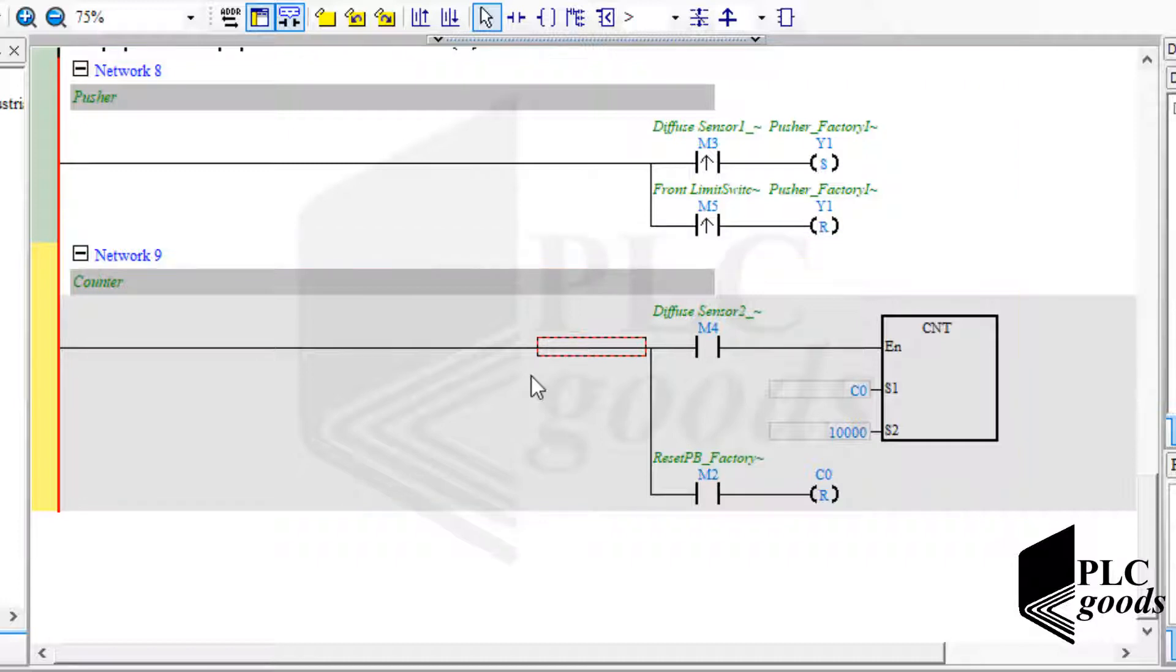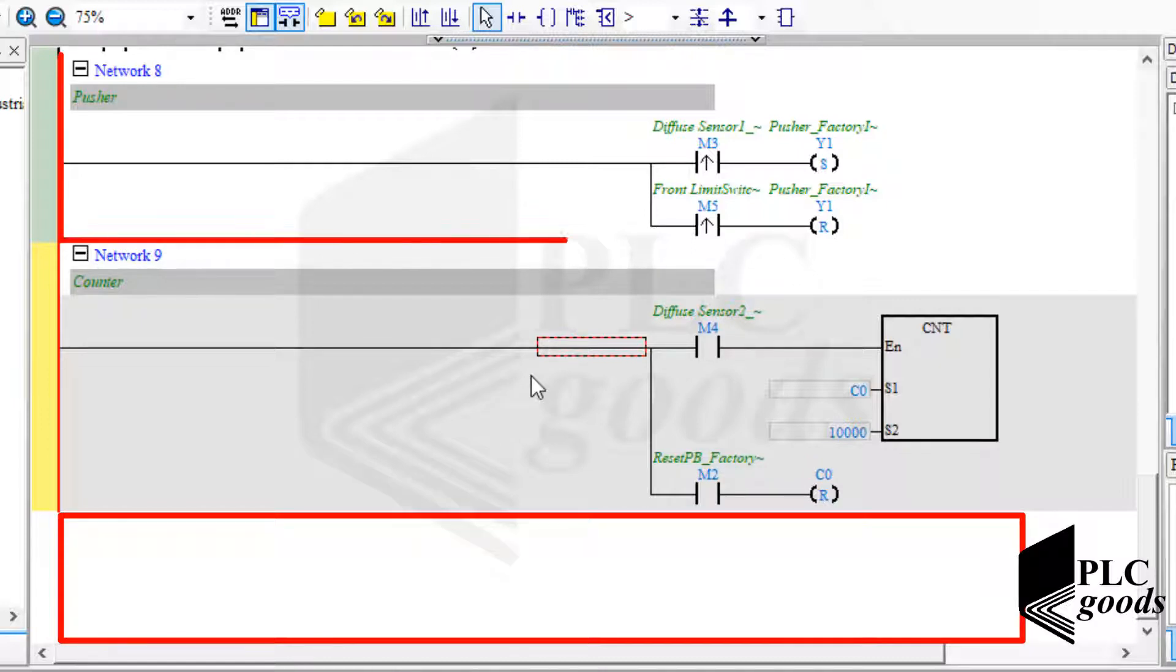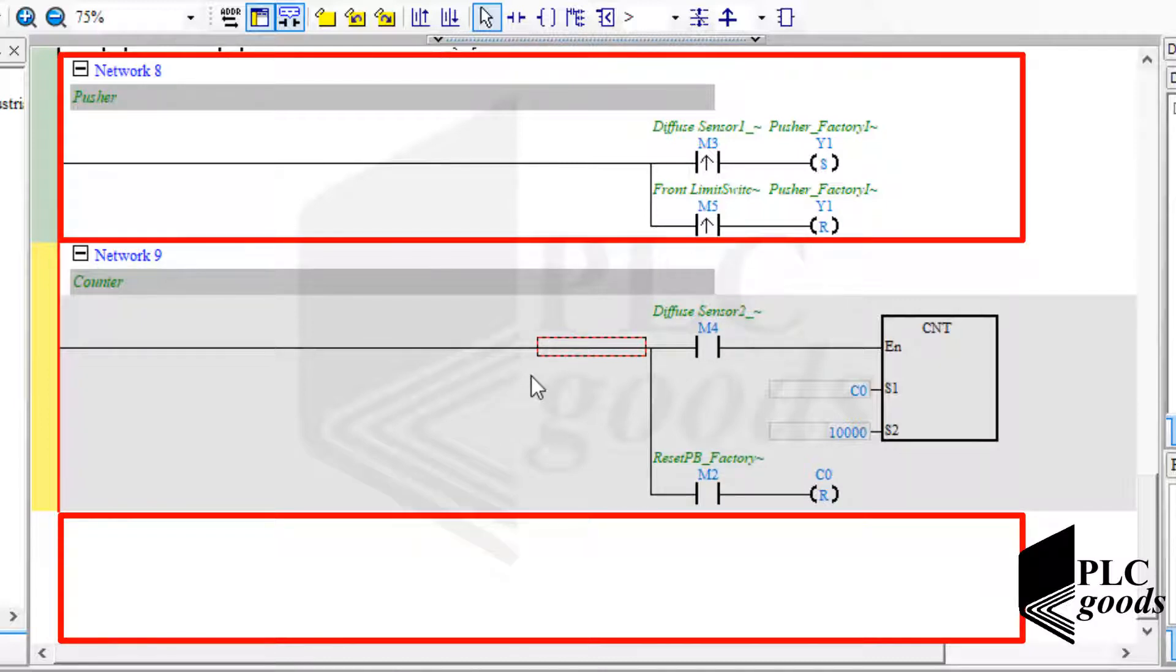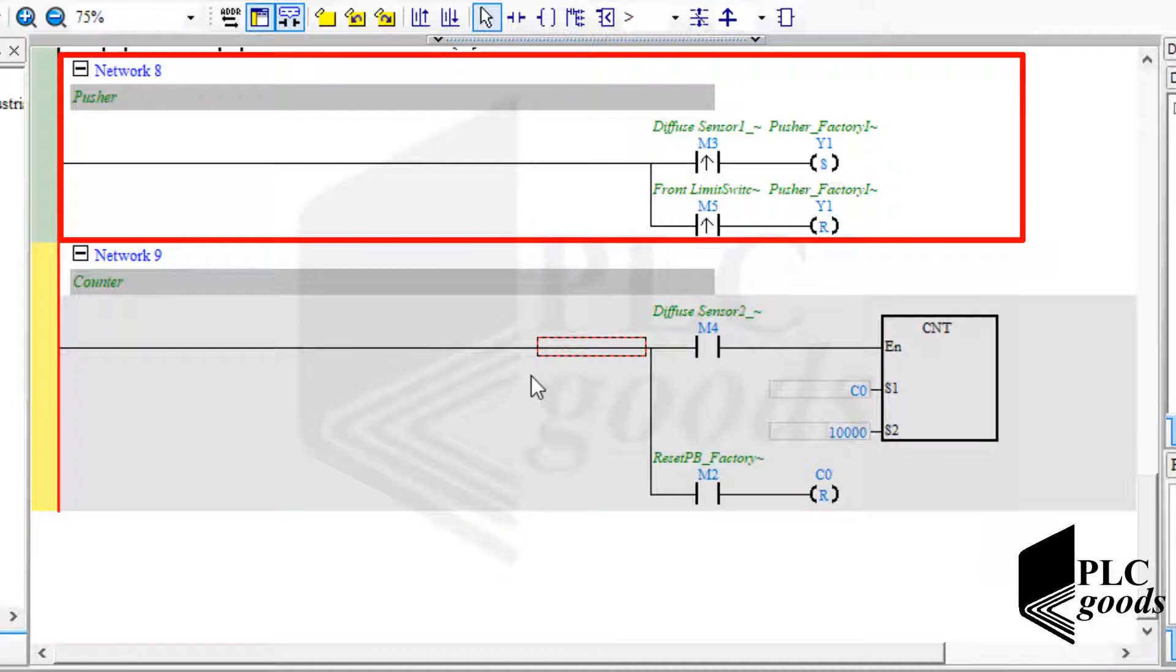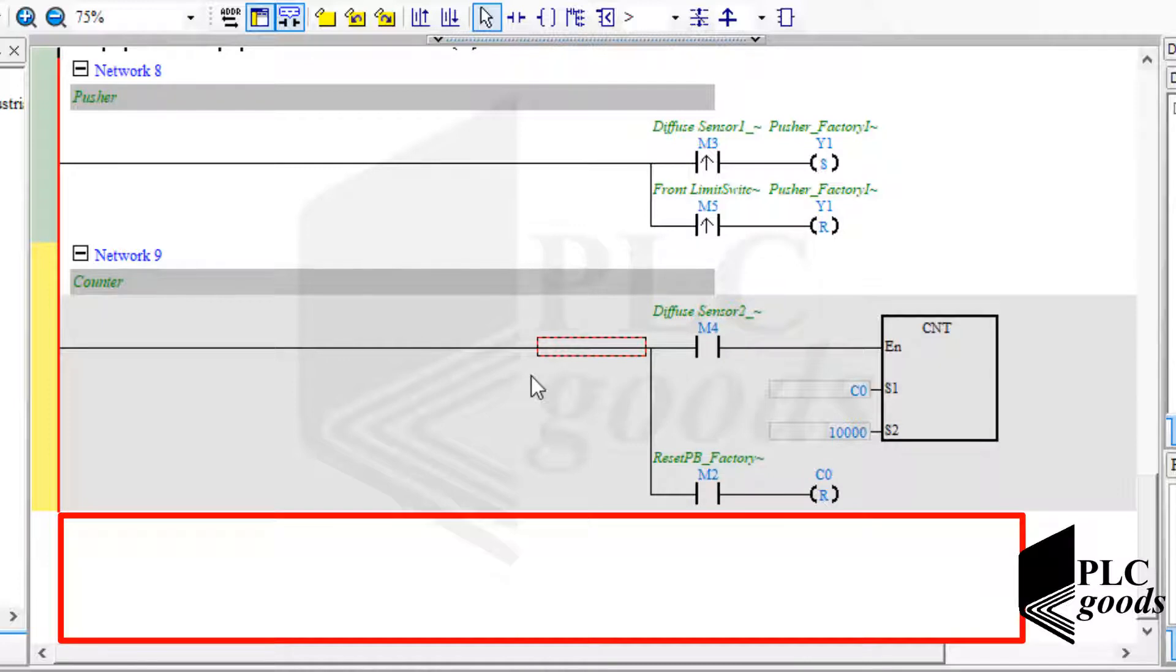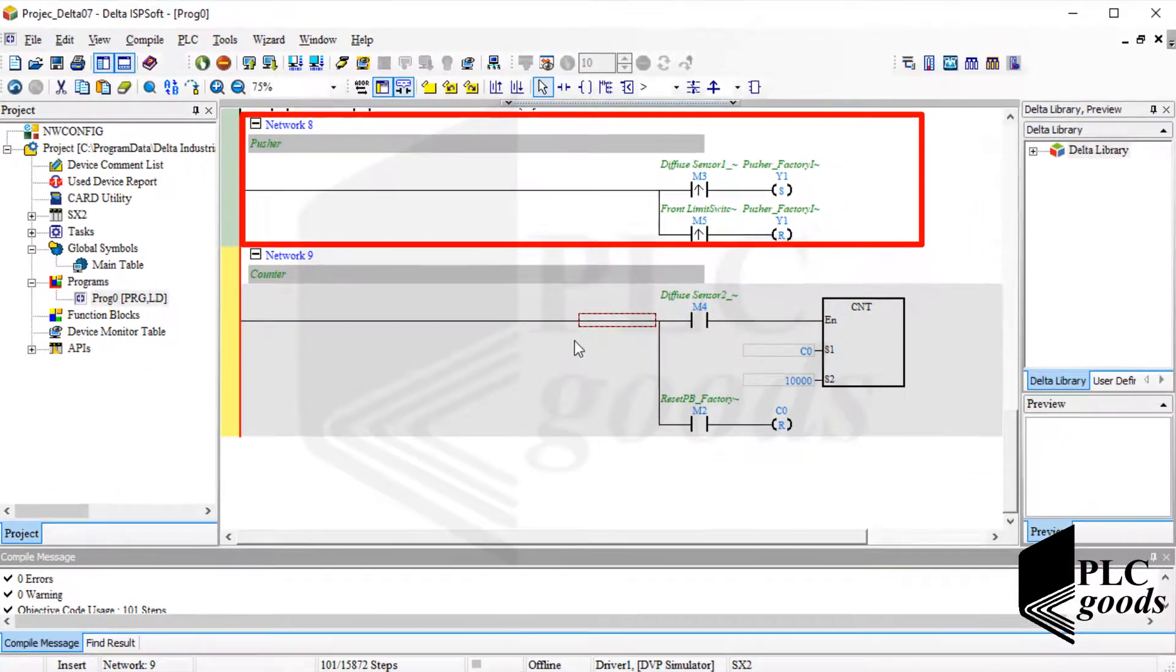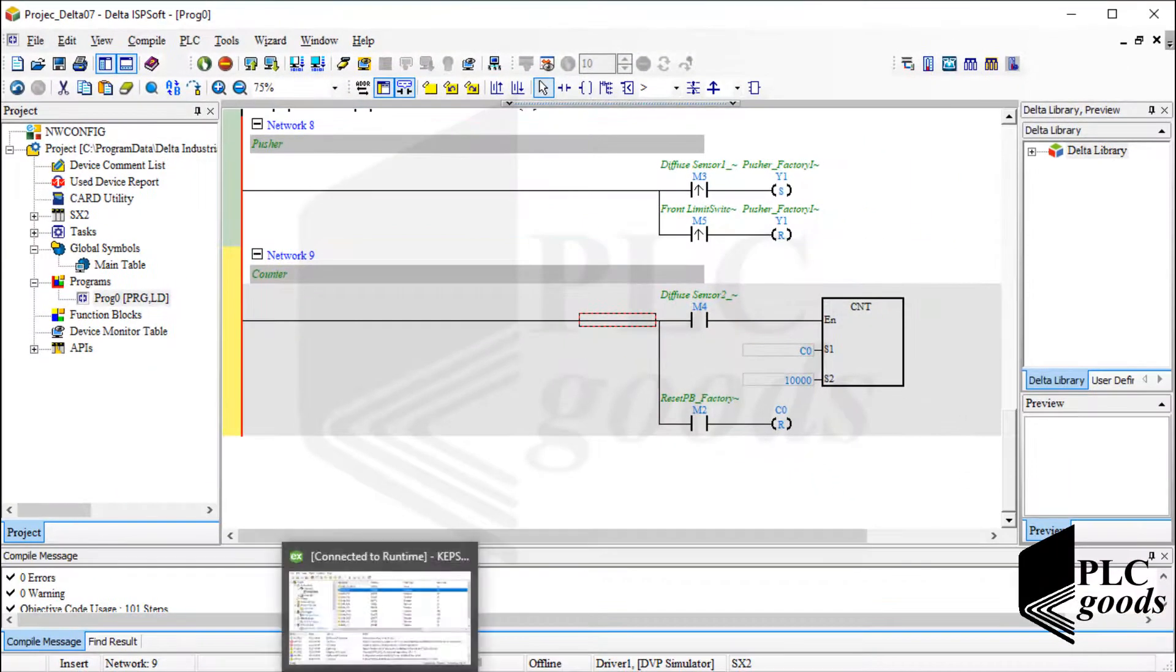Suppose here is another network that includes some conditions to turn on the pusher, like this network. So if this network decides to turn on or off the pusher, but the last network has another decision, PLC will work based on the last network and this part of my program will be ineffective.